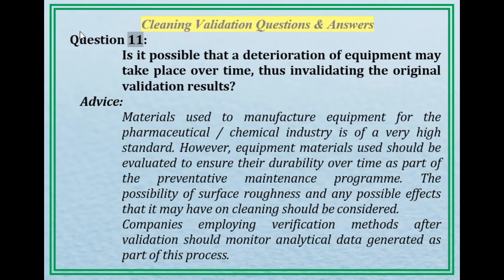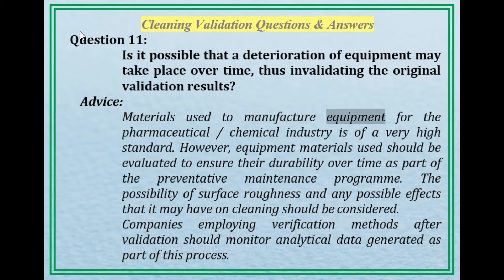Question 11: Is it possible that a deterioration of equipment may take place over time, thus invalidating the original validation results? Advice: Materials used to manufacture equipment for the pharmaceutical/chemical industry are of a very high standard; however, equipment materials used should be evaluated to ensure their durability over time as part of the preventative maintenance program.